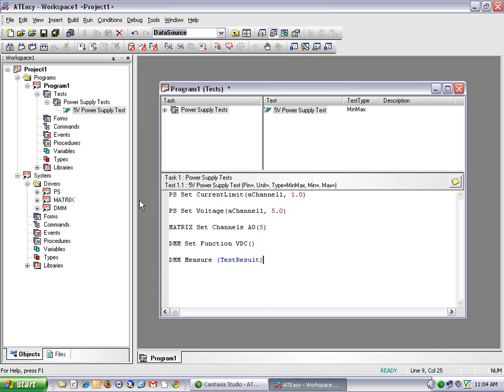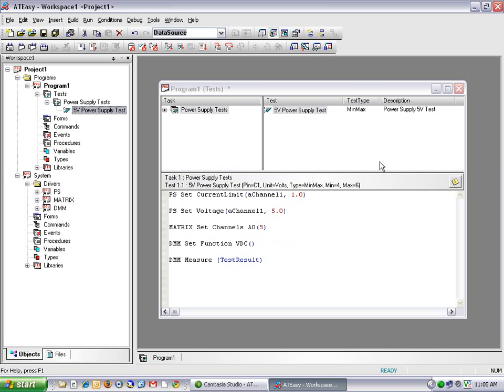Test result is a built-in ATEasy variable that stores the result after each test, and its contents are evaluated against certain parameters to determine pass-fail criteria. I'll right-click on my 5-volt power supply test and select Properties to set the test parameters — leaving the default min-max test type, entering the pin, setting volts as the units, and selecting 4 volts minimum and 6 volts maximum, along with a description for the test. Now I've created my first ATEasy test.